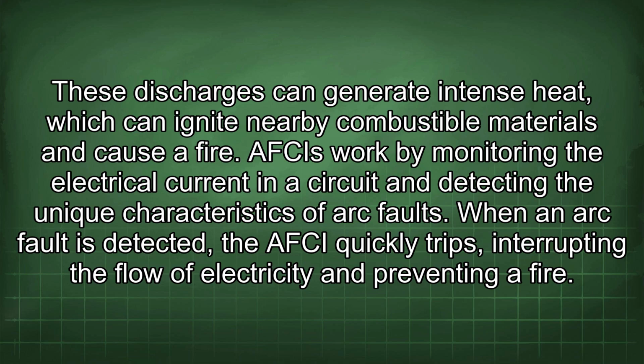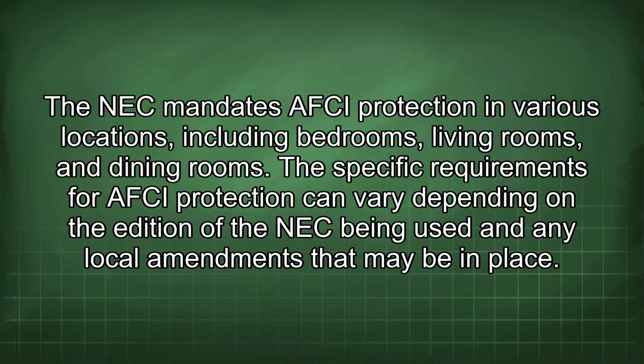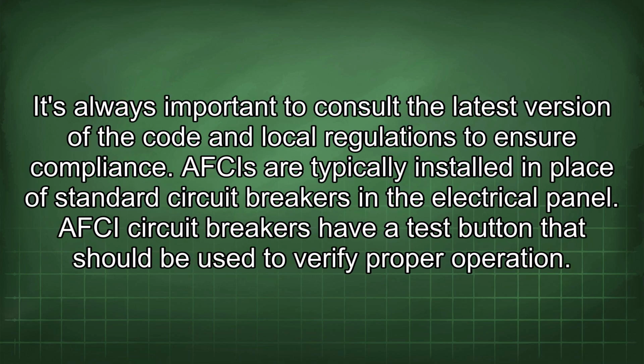AFCIs work by monitoring the electrical current in a circuit and detecting the unique characteristics of arc faults. When an arc fault is detected, the AFCI quickly trips, interrupting the flow of electricity and preventing a fire. The NEC mandates AFCI protection in various locations, including bedrooms, living rooms, and dining rooms. The specific requirements for AFCI protection can vary depending on the edition of the NEC being used and any local amendments that may be in place. It's always important to consult the latest version of the code and local regulations to ensure compliance.